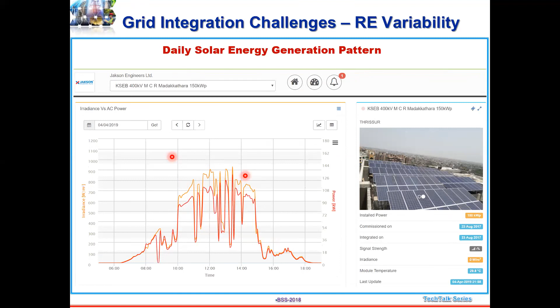So we have already talked about reduced fault level; reactive power issues will be there. Then the fluctuations: because of the low fault level, voltage regulation will be very poor, so there will be very big voltage fluctuation. I will show a case study which happened in the KSEB grid shortly. There will be voltage imbalances because of single phase injection in distribution grids. Then voltage rise will be there at the fag end, and reverse power flow will always be there.